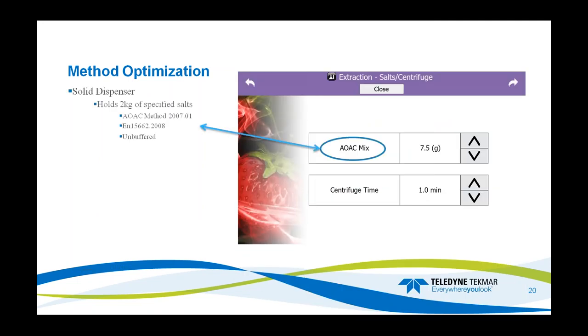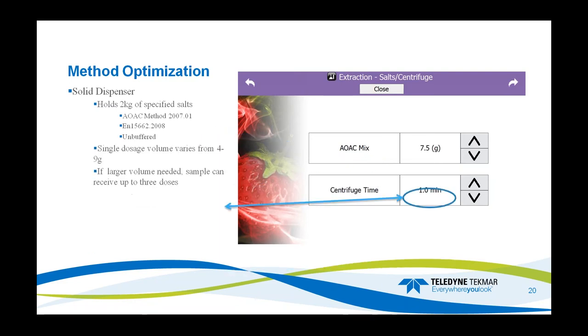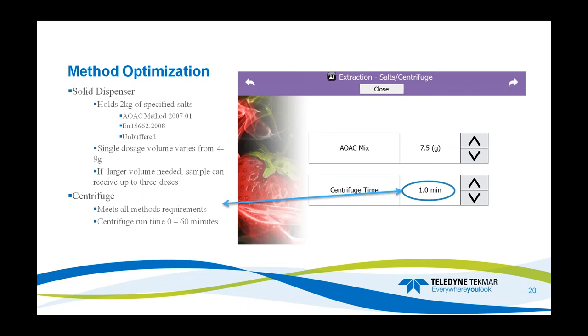The extraction solvents and centrifugation: the solid dispenser holds 2kg of specified salts — it could be the AOAC mixture, the EN mixture, an unbuffered mixture, or a custom blend. Single dose volumes vary from 4 to 9 grams, and if you need more than 9 grams the sample can receive up to three different doses. The centrifuge meets all method requirements across EN and AOAC and can run anywhere from 0 to 60 minutes.